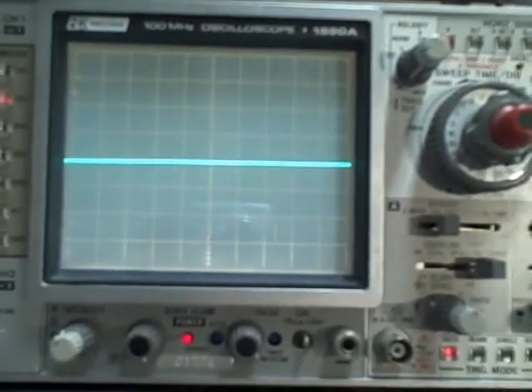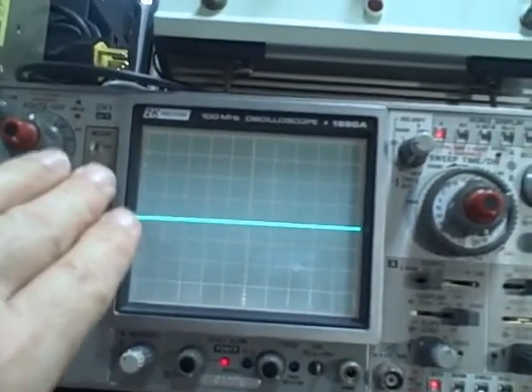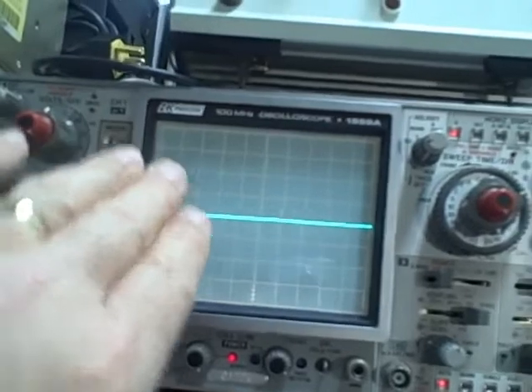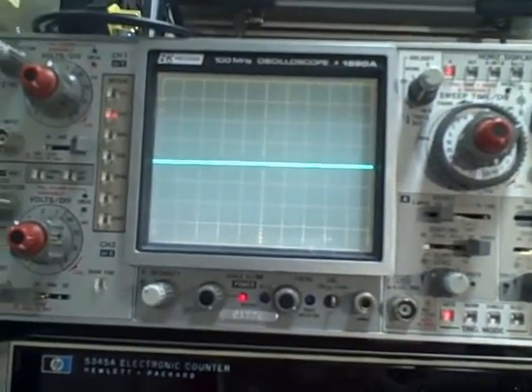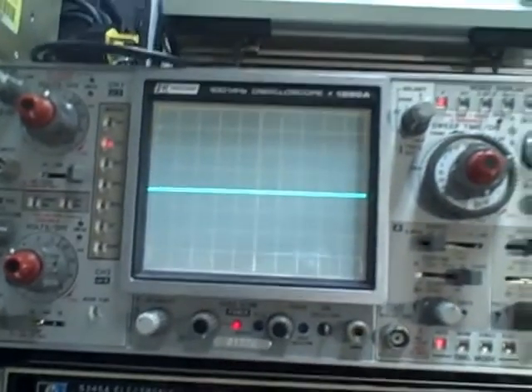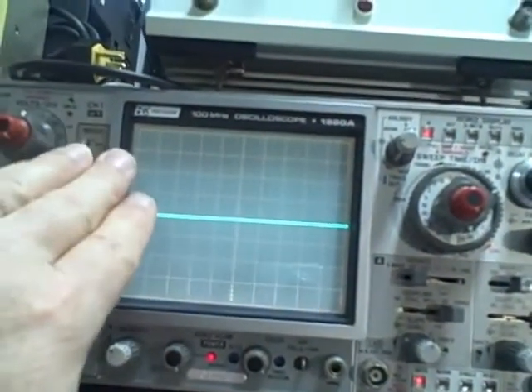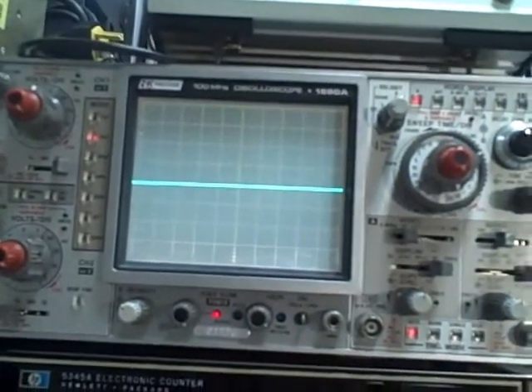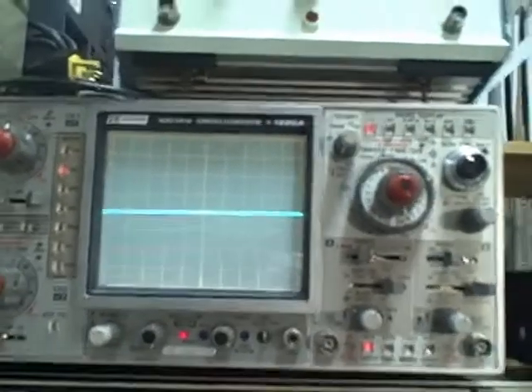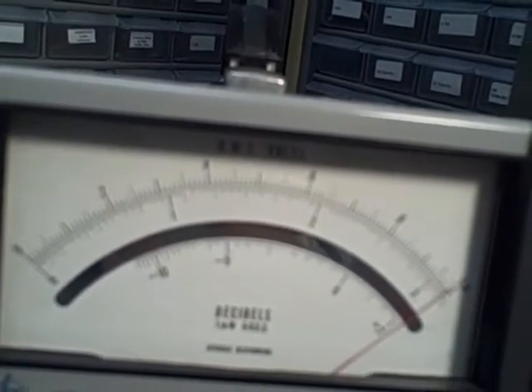We'll adjust for 1 volt full scale. We're going to take a look at our oscilloscope, and we're going to see what that represents on the scope. Right, we're just going to look for relative peak. So we're going to know that whatever we achieve on the scope when the meter is showing full scale is what we want to show on the scope when we switch our frequency higher. We'll adjust again to get the same value on the scope, and then we'll take a look at the meter and see what we hit. So let's give it a try. Right now we're a little less than full scale, so we're going to raise ourselves up. That looks to be dead on.